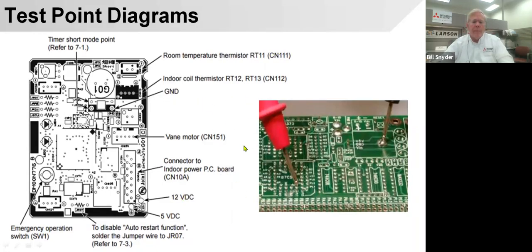When you open up the top of some of our units, you look at this circuit board and it's upside down. But in the service manual, there are test point diagrams that actually show the underside of the circuit board, so that you can say that if I go between this point here and this point here, I should be getting 12 volts DC. If I go between here and here, I should be getting 5 volts DC. You can actually look at the thermistor and everything from the top side. So you can do a lot of your testing from the back side here without having to lay on your back and look up or try to get the circuit board out of there. So that makes it a little easier.